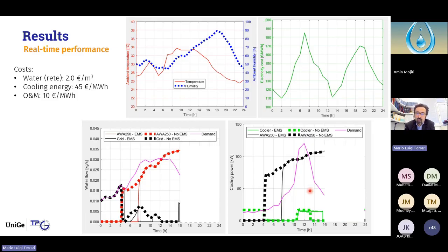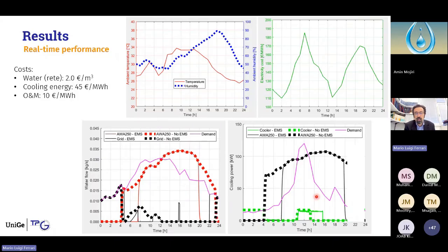Then it's possible to see that the heat pump has been deactivated, and finally we also have the activation of the AWA250 when the demand for cooling and for water became low, like after 8 p.m. In the final part of the day, we have again some utilization of the storage, and then finally no further activation of the AWA250 because it was not considered useful.